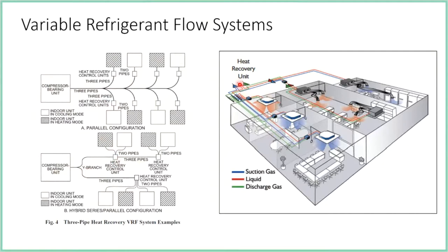So one of the benefits is you have a three-pipe system, and a couple of manufacturers do it a little bit differently, so everyone has their own way of doing it. The principles are really the same, and that is I can move the heat that is being generated in these spaces. These look like meeting room spaces here, and I can recover it, and I can supply it into an office space that needs a little bit more heating. And if I look at the overall system, I'm able to recover it. And now if I think about my energy efficiency, remember we have my 3/8 refrigerant, 2 inches of a hydronic, and 42 inches of duct, and I'm an architect, I have a lot less space that has to be taken up for mechanical equipment. So again, one of the great advantages of this system.